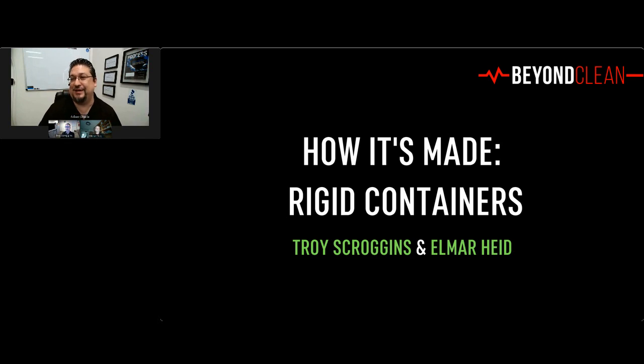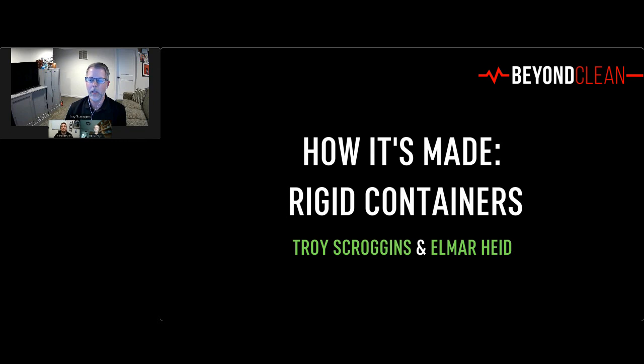So that's great. We talked about stacking the sets, and our urban legend that you can't stack the solid bottoms, which is false. So how high can they stack the instrument sets, and why is there a limit? In our IFU, 18 inches is our limit for the U.S. I don't know if the global standard is a little different, but for the U.S., that's ours. So why is there a limit?